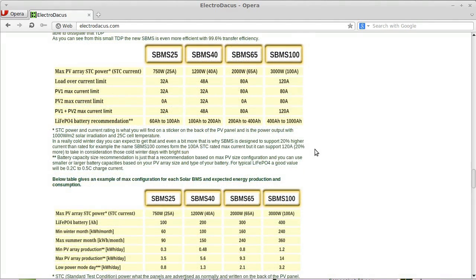So I named this SBMS 25, even though the overcurrent limit for both input charging and discharging is 32 amps, because if you look on the back of a solar PV panel for its specification, the values are for the standard test done at 1000 watts per square meter of solar radiation and at 25 degrees Celsius for the cells. But normally in summer they are at higher temperature, so they'll output less power than specified.